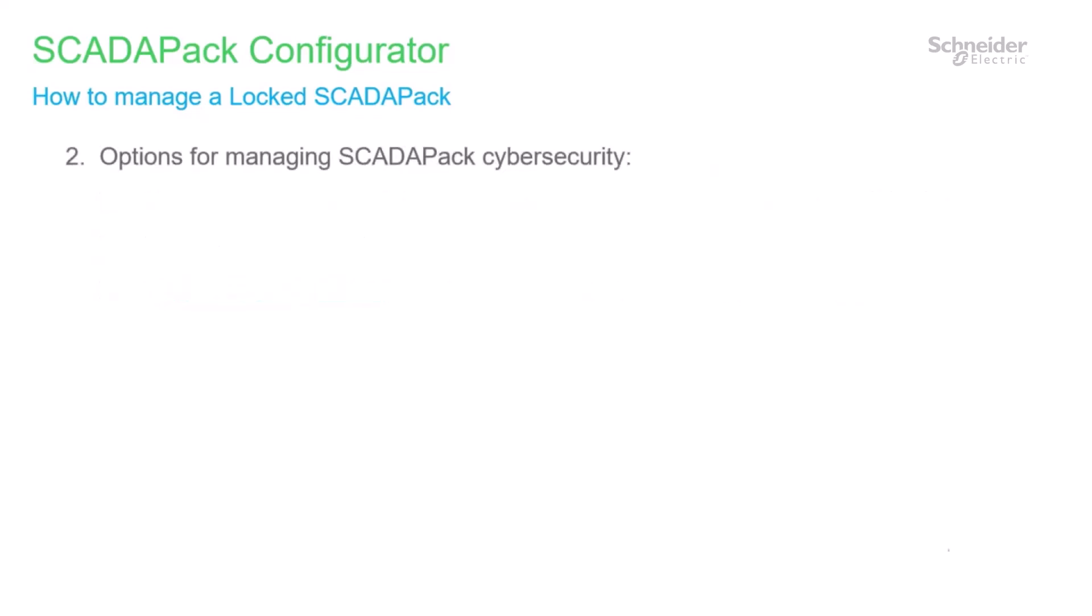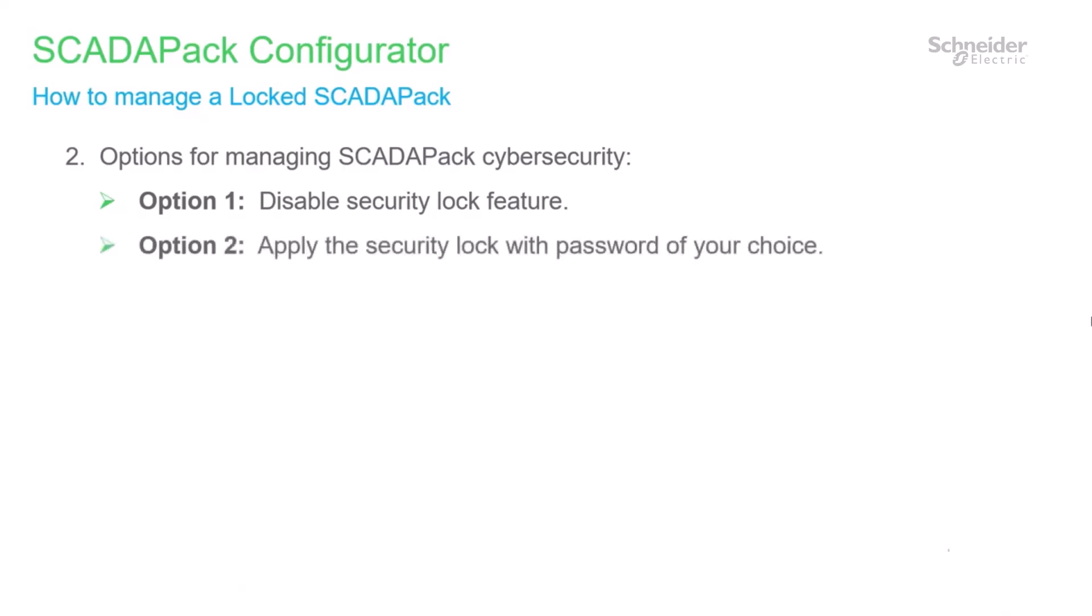Once updated to SCADAPack Configurator 1.3.1 or newer, you will have three choices for managing the secure lock on your new SCADAPack. Disable the security lock feature. If the security lock feature is desired in the future, a cold boot or service boot will re-enable it. Or, apply the security lock with a password of your choice. Or, downgrade the controller's firmware to remove security locking altogether.